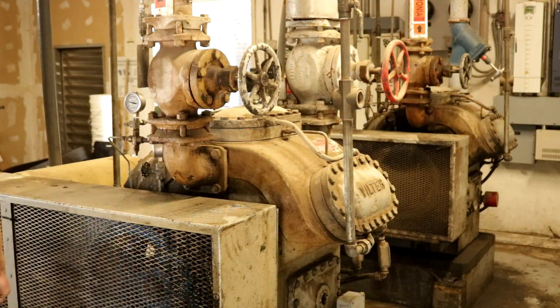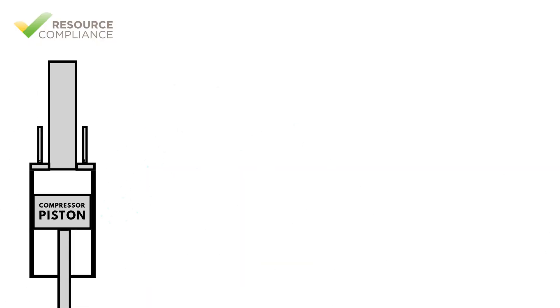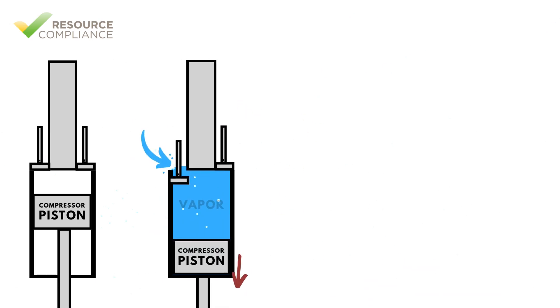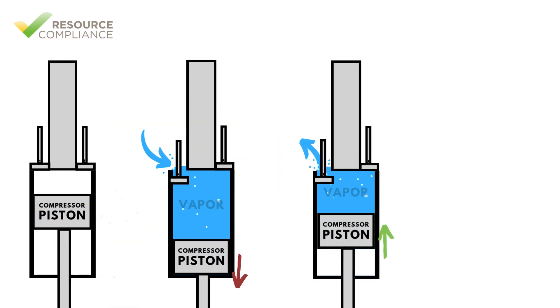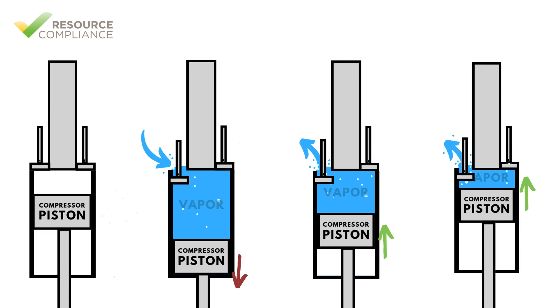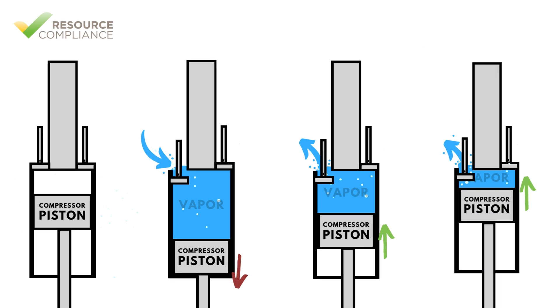Cylinder unloading is accomplished by forcing one or more cylinder suction valves open. During the intake stroke, vapor will be drawn into the cylinder, but since the suction valve is forced open, no compression will take place during the compression stroke and the vapor will simply exit through the suction valve from which it entered.